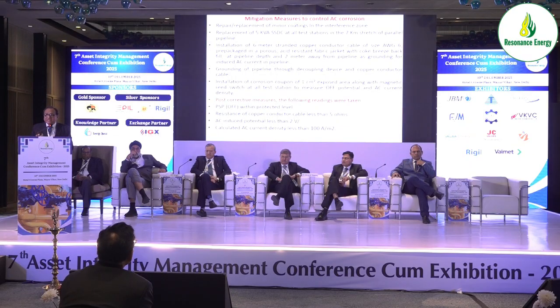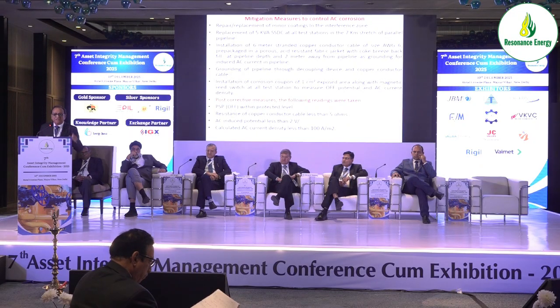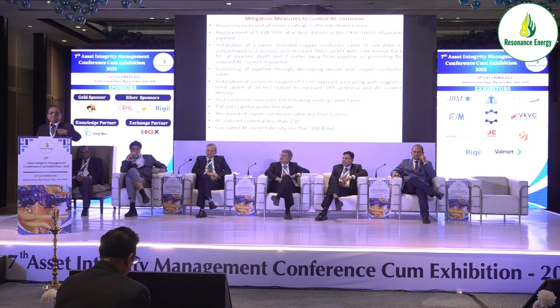So what is your cycle? You are taking 30 cycles, that is 0.6 seconds, 600 milliseconds. Don't rely on electrical authorities. Their breaker may not flip, but your pipeline may get damaged. Go for 3 cycle or 5 cycle current, with 10 kiloampere at 220 kilovolt. Will 5 kiloampere at 600 milliseconds be safer for your pipeline?